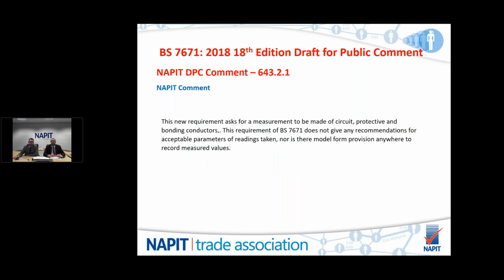So we intend to comment in so much as the new requirement is asking for a measurement to be made of the circuit. However, it's not giving any acceptable parameters for the readings that you should maintain. So it's asking you to measure something, but not giving you a reading to compare it against. And once you've taken that reading, there's nowhere to put it down. There's merely a tick box. So we feel that at this juncture, you can't really do that. You either need to change the way the new regulation or the draft is worded, or make some changes elsewhere and put some more information in. But at the minute, we feel it's lacking.